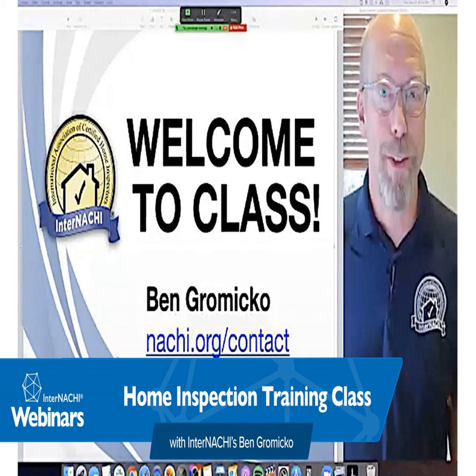And this is the full report. So we can go here: correction and further evaluation. The filter is being sucked into the blower fan. It hasn't been serviced and cleaned in over a year.